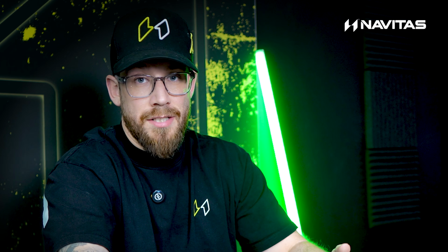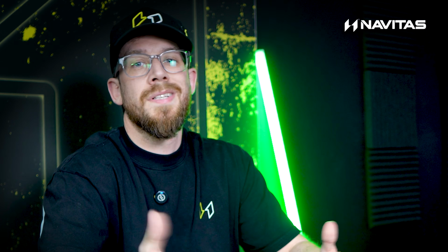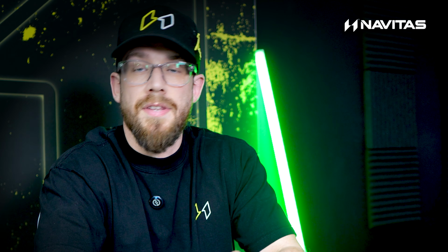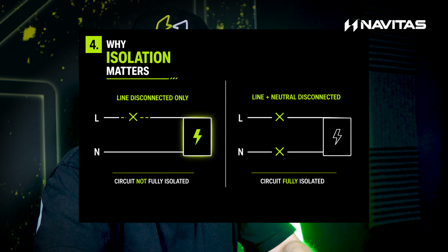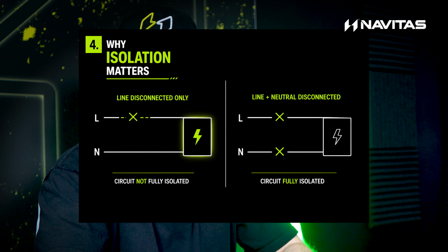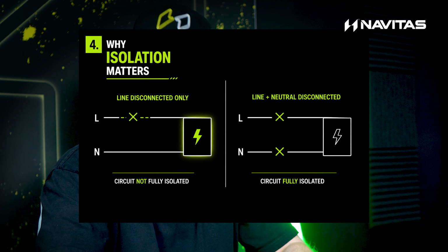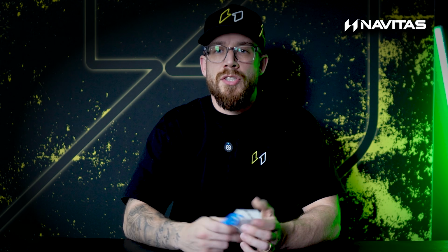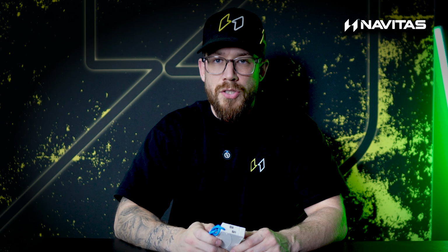So on a TT system, the neutral is referenced back to the supply transformer. Under normal conditions, it'll be close to earth potential, but it's not guaranteed to stay at 0 volts in every situation. Things like load imbalance, things like volt drop, some fault conditions can actually result in some potential appearing on the neutral. So if only the line conductor is disconnected, you can still have a live current on the neutral side. So let's have a look at the different RCBOs that we can choose from.